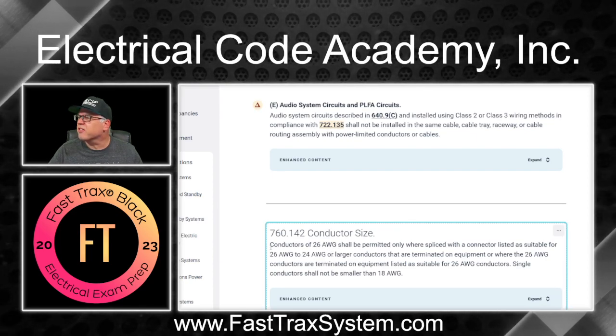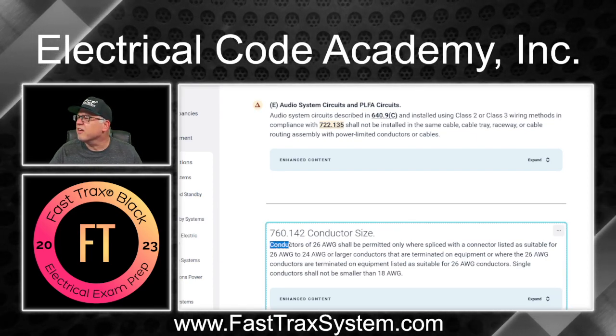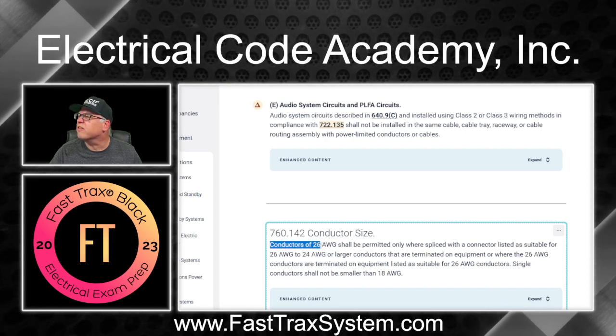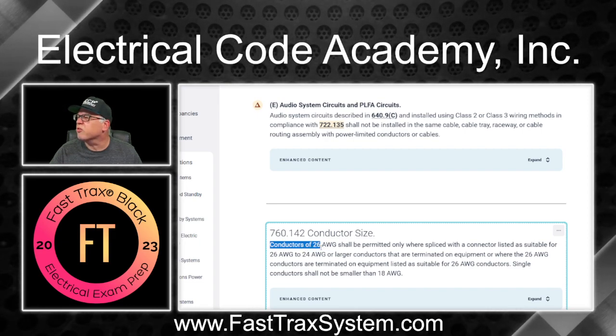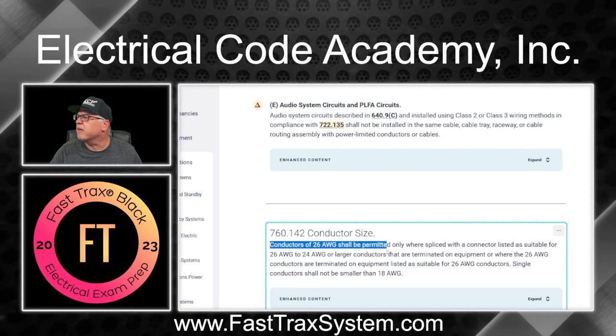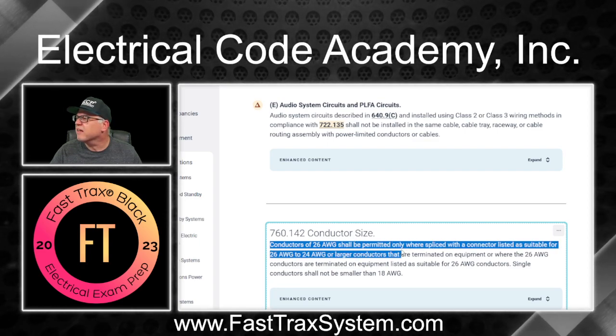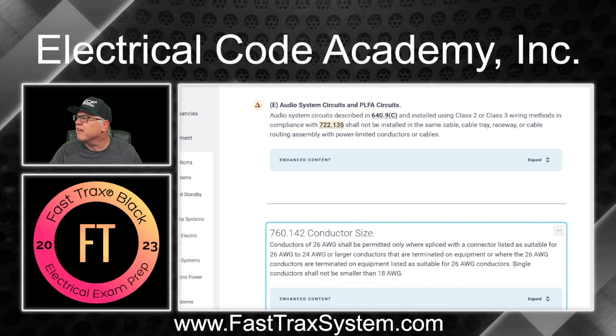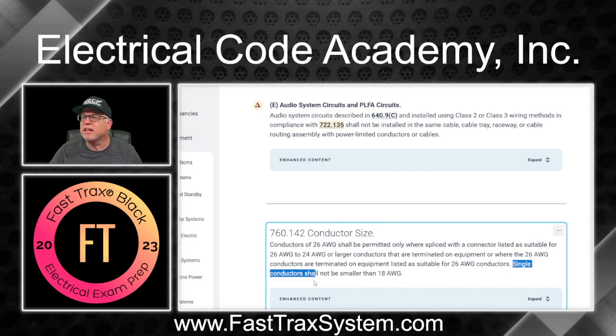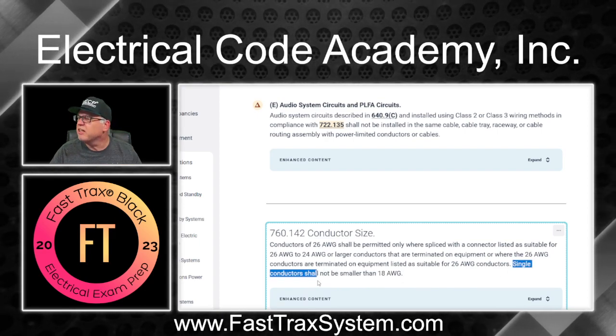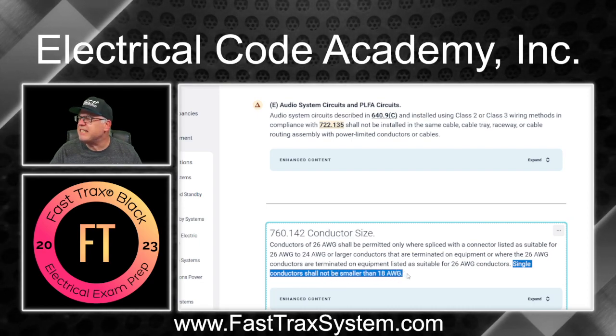It says conductors of 26 AWG shall be permitted only where the splice, okay, and then it goes right here. It says, lastly, single conductors, and that's what we're talking about. Single conductor shall not be smaller than 18 gauge.